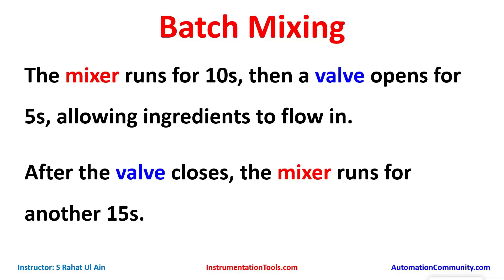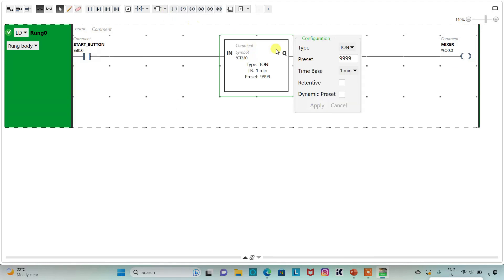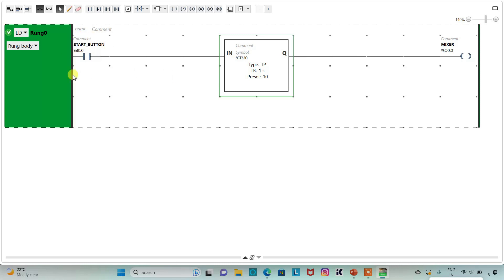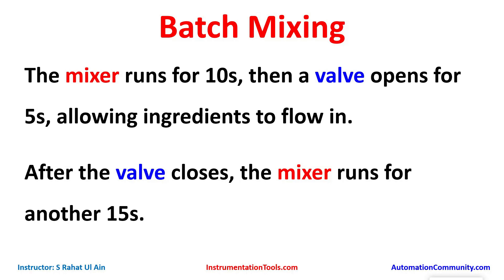I will assign the address I0.0 to the contact with the symbol 'Start Button', and assign address Q0.0 to the coil with the symbol 'Mixer'. Since the mixer runs for 10 seconds, I will use a TP timer. I insert a functional block timer, change the type to TP, time base to 1 second, preset value to 10, and click Apply.